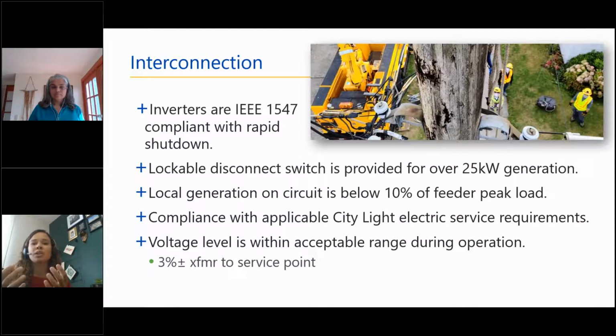Here are some of the interconnection considerations done in the impact study. Inverters were IEEE 1547 compliant with rapid shutdown. They had a lockable disconnect switch, because it was 25 kW or over. Local generation on a circuit was below 10% of the feeder peak load. And with the lockable disconnects, we have multiple disconnects - I think there's one on the pole, and then disconnects for the battery and equipment - making sure all those exist for the system.